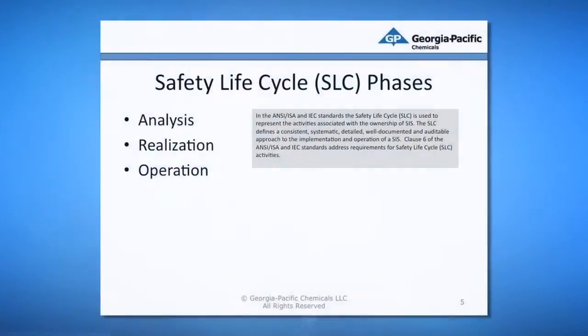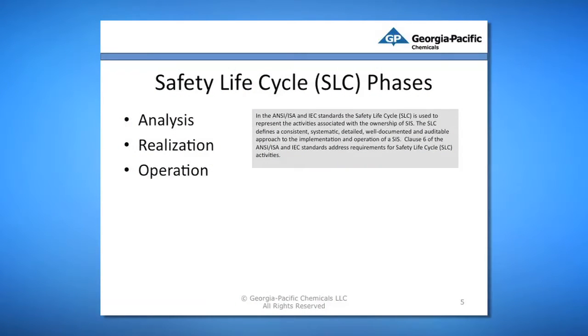Based on the standard, there are three phases of the safety life cycle management. The phases are analysis, realization, and operation. We're going to take a look at each of these next. In the analysis phase, all the potential risks and their consequences are identified, and the layers of protection are analyzed. This leads to development of non-SIS protection layers, and finally to identification of the need for a SIS, including the requirements for the SIS.